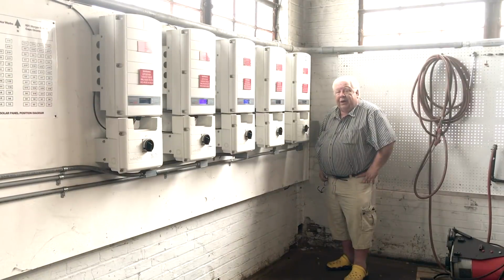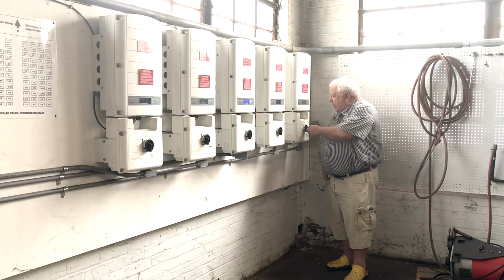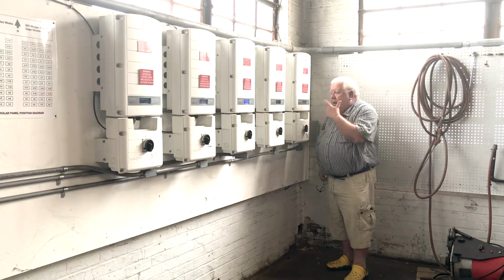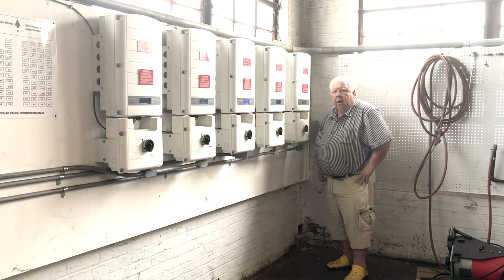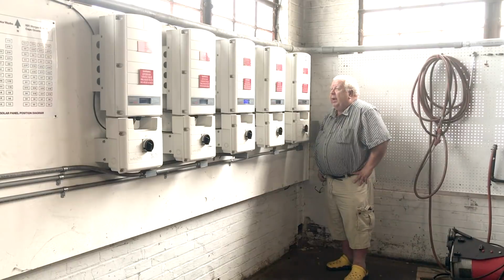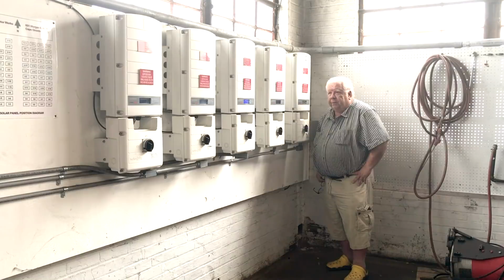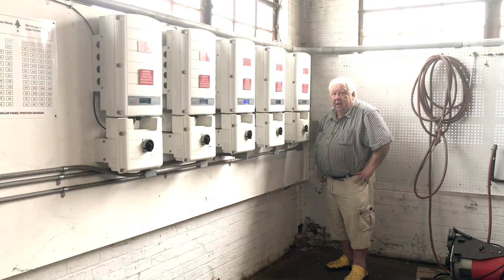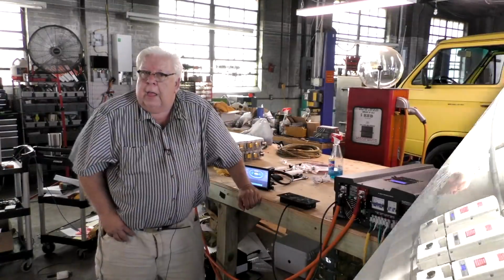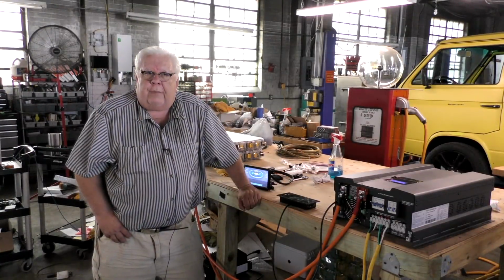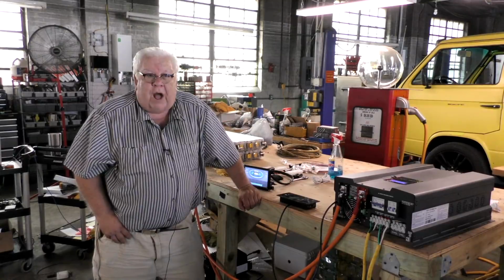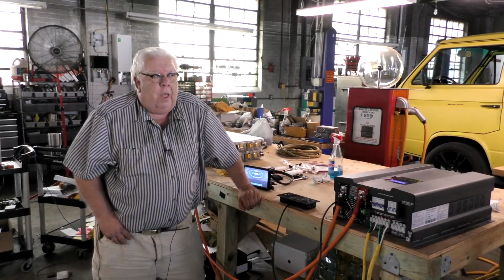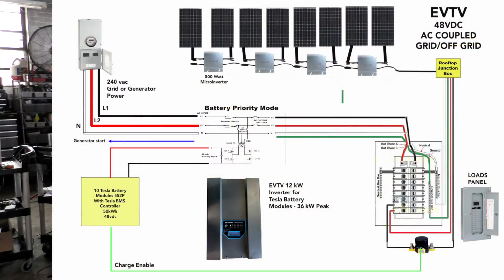We're back at our grid-tied inverters, the Solar Edges. I'm going to turn on number 5. Again, 300-second time delay, and we will bring that back up on our system and see what effect that has on our 12 kilowatt 48 volt inverter and battery system. I'm going to put up a diagram here while we're waiting for number 5 to time out. And so I'm going to put up a diagram of what we're doing here.